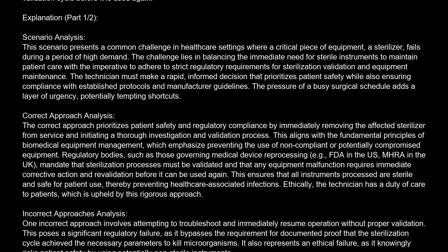This aligns with the fundamental principles of biomedical equipment management, which emphasize preventing the use of non-compliant or potentially compromised equipment. Regulatory bodies, such as those governing medical device reprocessing, e.g., FDA in the US, MHRA in the UK, mandate that sterilization processes must be validated and that any equipment malfunction requires immediate corrective action and revalidation before it can be used again. This ensures that all instruments processed are sterile and safe for patient use, thereby preventing healthcare-associated infections. Ethically, the technician has a duty of care to patients, which is upheld by this rigorous approach.